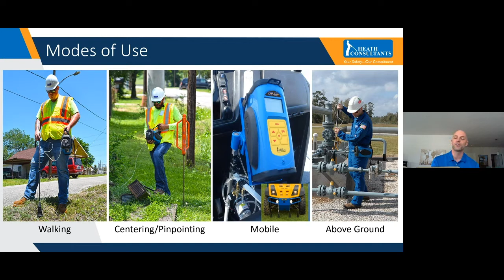So how the DPIR actually works, and when I get into the description of how these products work, I'm not an engineer, so I like to try to get it into the most layman's terms possible. The DPIR is a pump-driven instrument. Once the sample is taken into the instrument, inside there's a chamber. In the chamber, you have the infrared light, and on the other end, you have a collector cell. Under normal circumstances, when there is no methane present, you have no interruption of that light going across the chamber. When you have an interruption, that's caused by methane, and the DPIR is selective to methane. It's not going to false alarm on other hydrocarbons. So when methane gets in that chamber, that light is interrupted, and based on the amount of interruption, it's going to give you either a parts per million or a percent gas reading. That's the simplest way I can explain it.